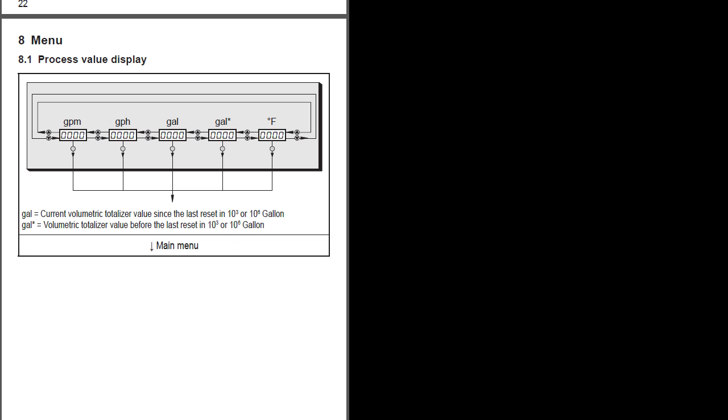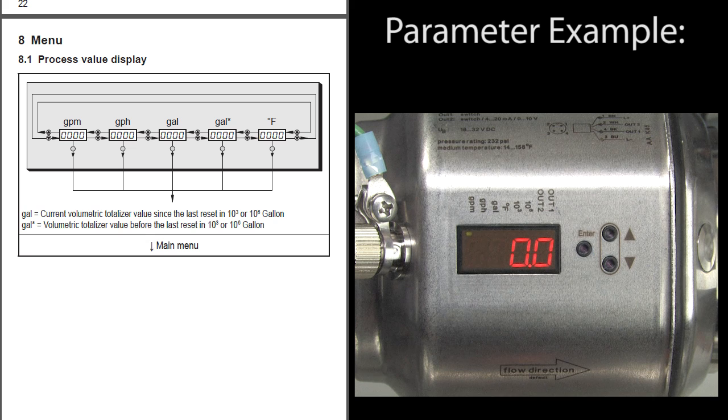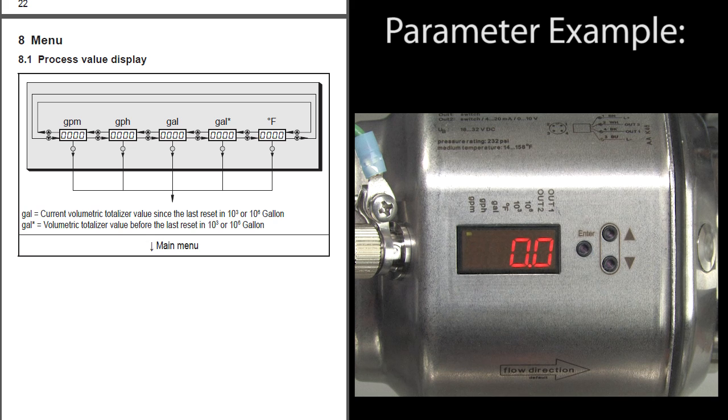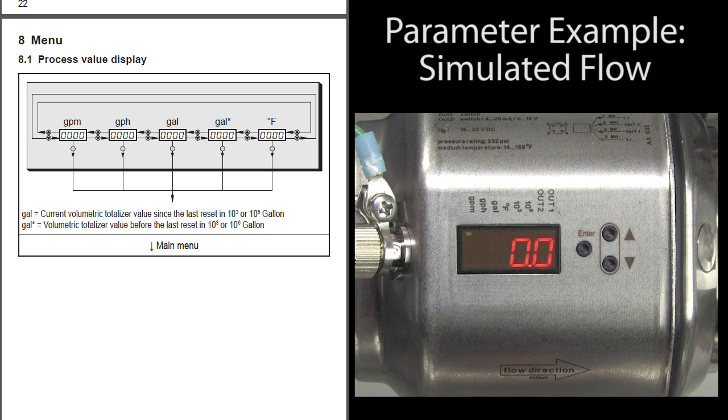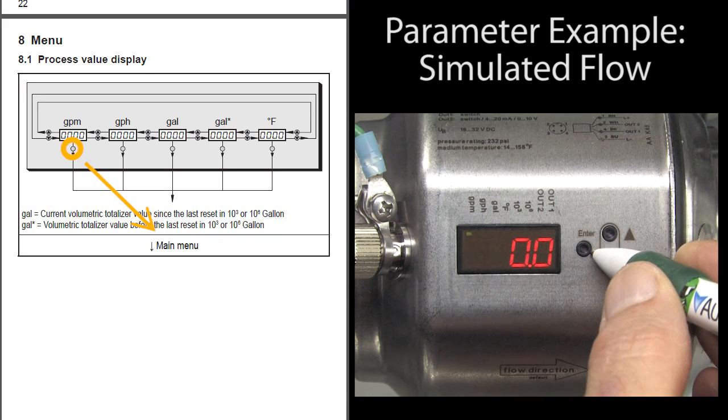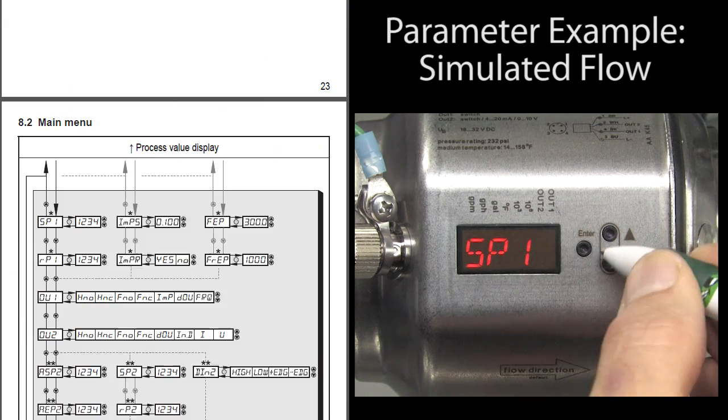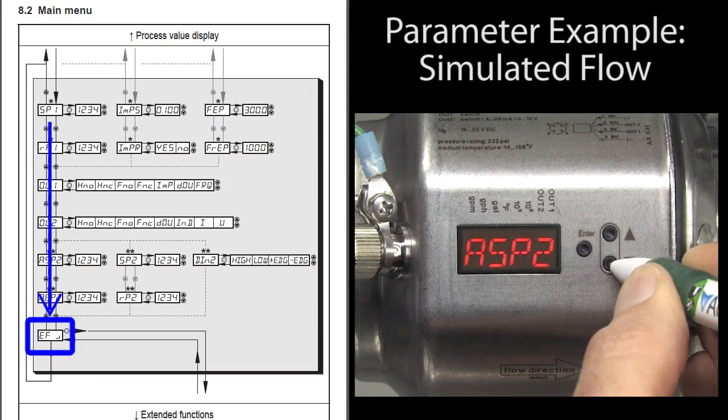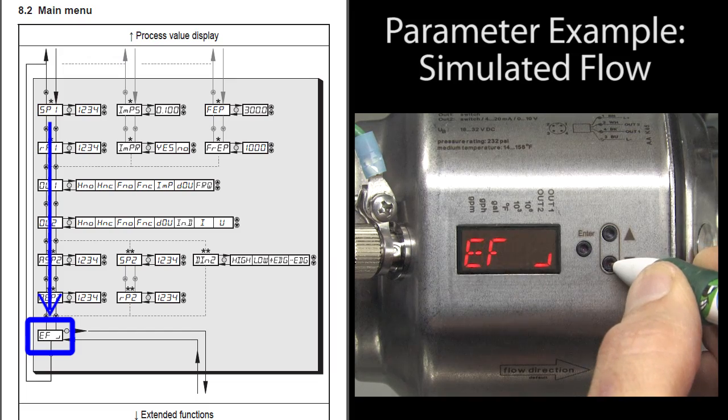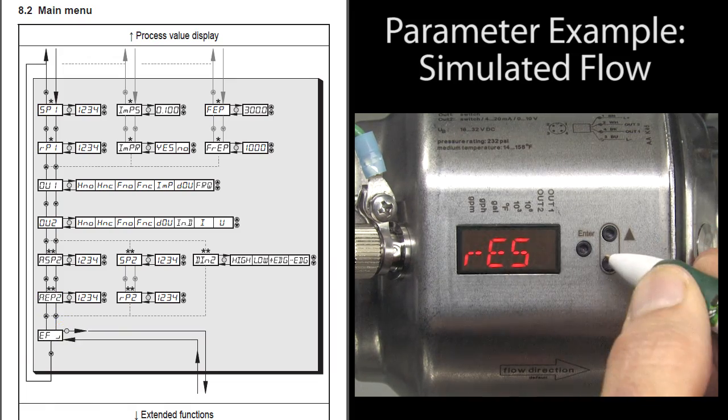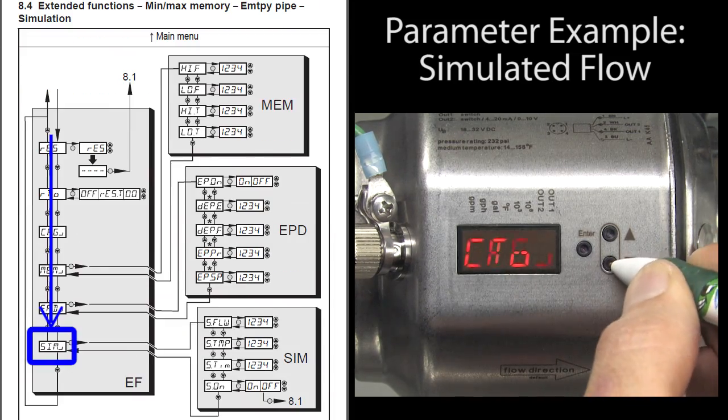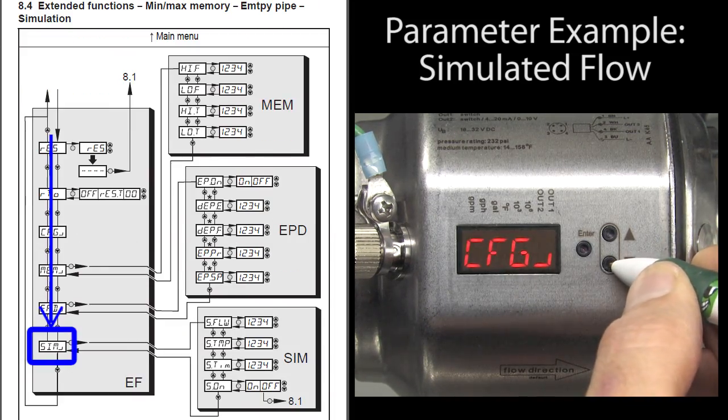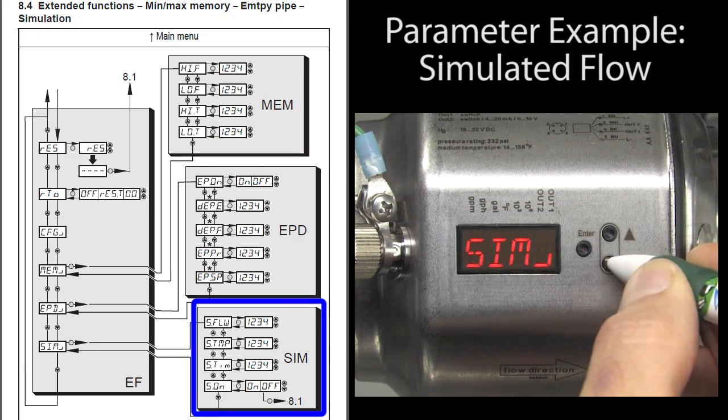Let's do an example so you can get a feel for how parameters are set on this flow meter. One of the cool things you can do with these larger flow meters is you can simulate the flow. Press enter to drop into the parameters and then arrow down to the EF menu – that's the extended function menu. Press enter to drop into that menu and then scroll down to the SIM menu and press enter to drop into that.